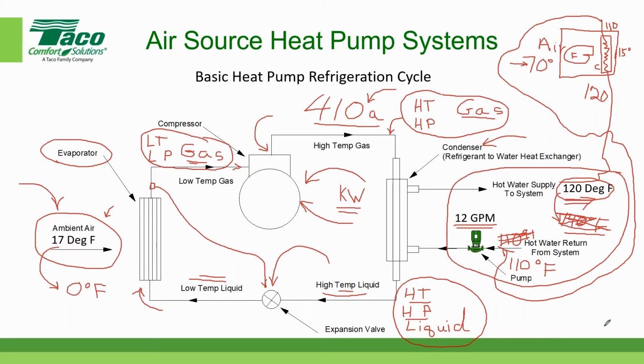So to ensure that you always have enough capacity, some manufacturers will put an electric resistance heater inside of their cabinet. And I'm just going to arbitrarily draw a little box here and make this an electric heater. Here's a couple of electrical connections right there. See those electrical connections, Brett? Yep. They look like a plug. Inside here is a heating coil. And the control system will say, hey, you know what? My ambient temperature is so low, it's not a very efficient way of making heat from my compressor. So I'm going to shut the compressor off and run my electric resistance heat. So I'm going to put an RH here, RH for resistance heat.